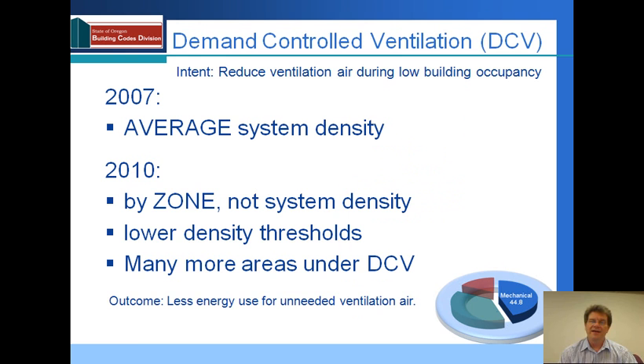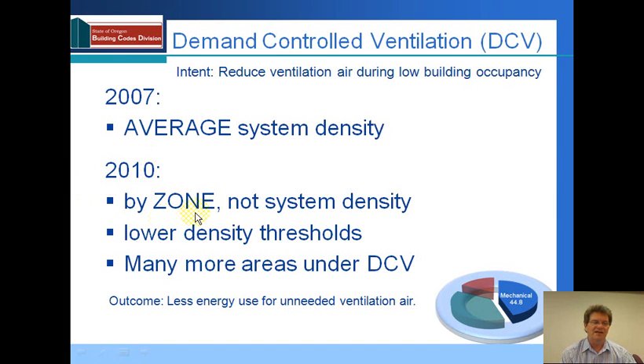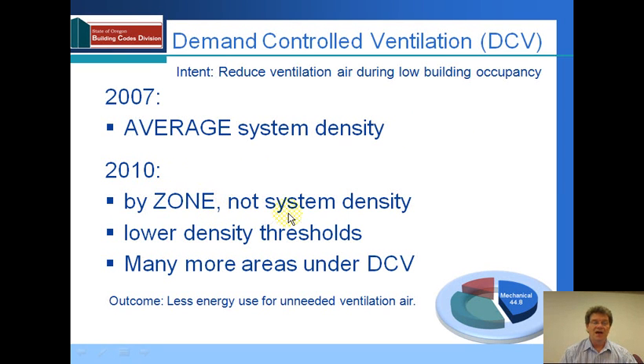Demand-controlled ventilation has a significant change. Demand-controlled ventilation was required in the prior code, but based on average system density. This typically meant that when you had one unit serving an area with a high density — say a classroom, a gymnasium, or a large auditorium or movie theater — you would have demand-controlled ventilation required. This new requirement is by zone, not system. Under the old code, if you had one zone on a large system, it would average out so that the density requirement was not triggered and demand-controlled ventilation would not be required. In the new code, it's required by zone, not by system.